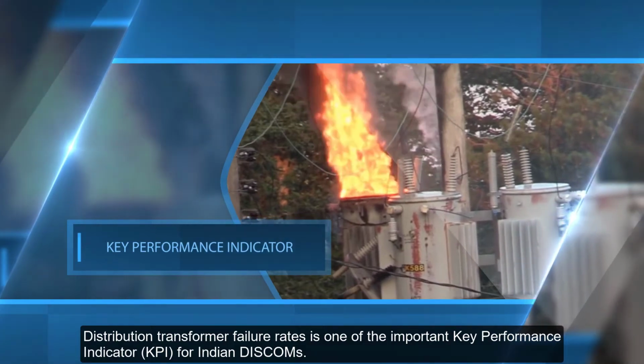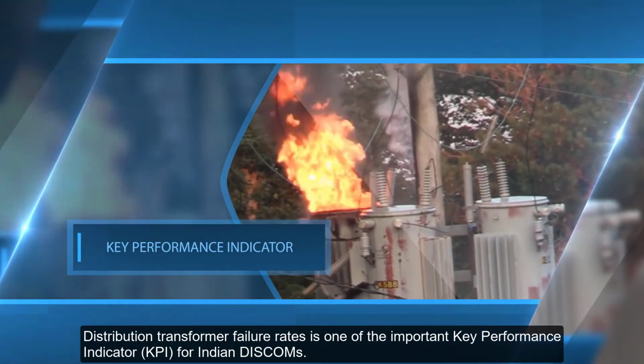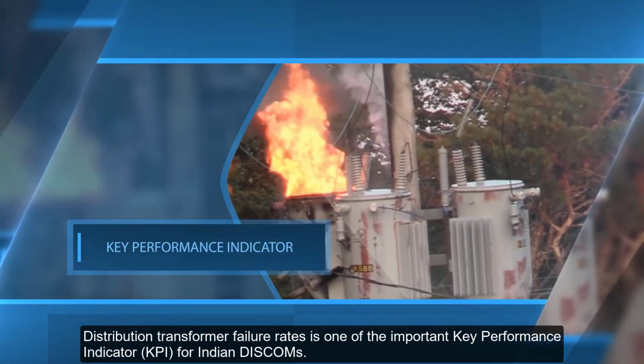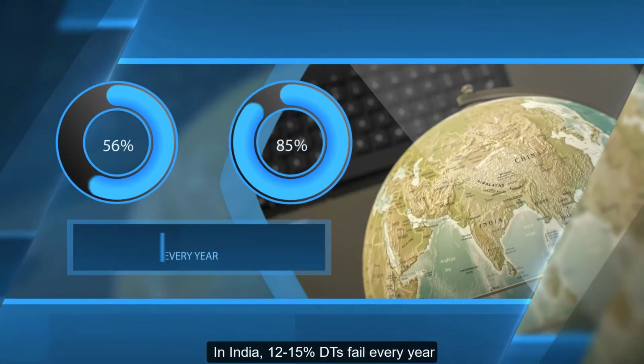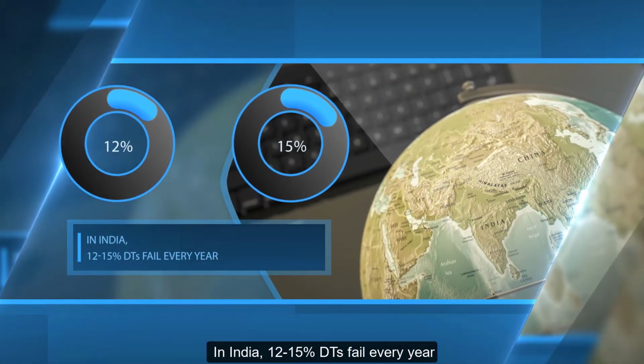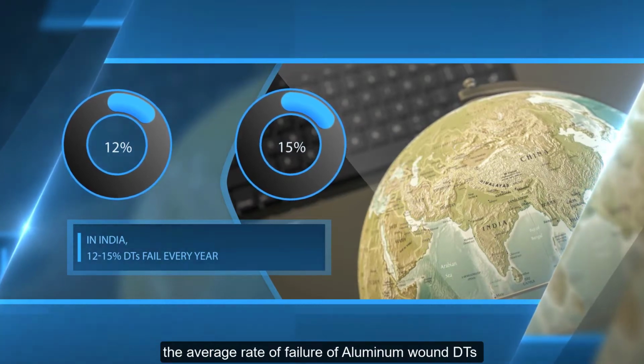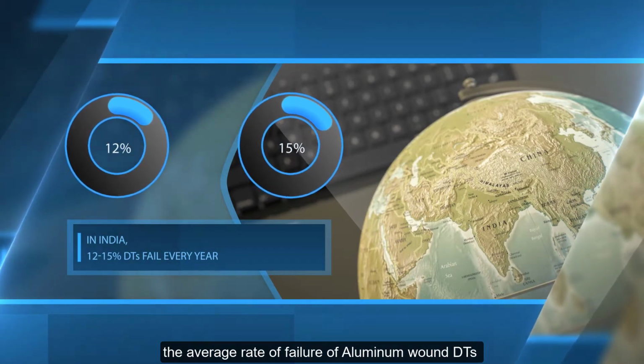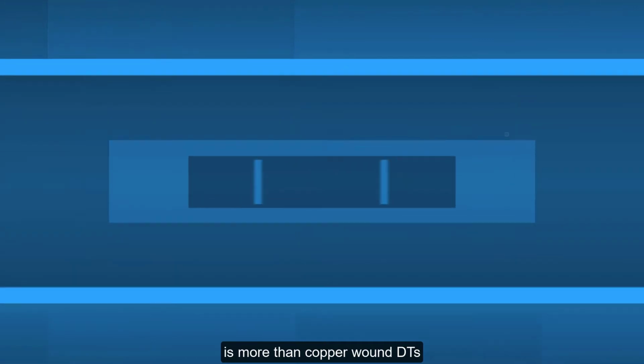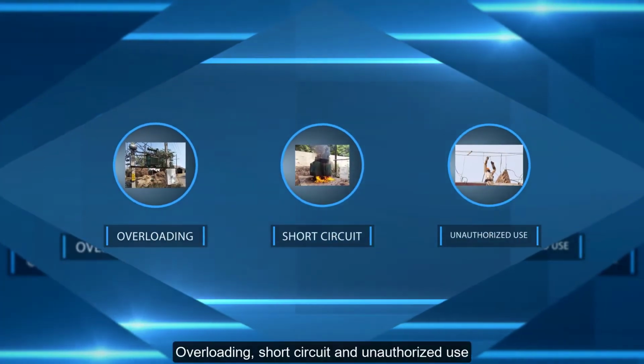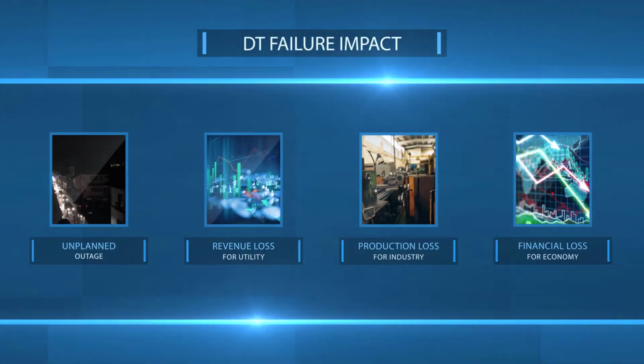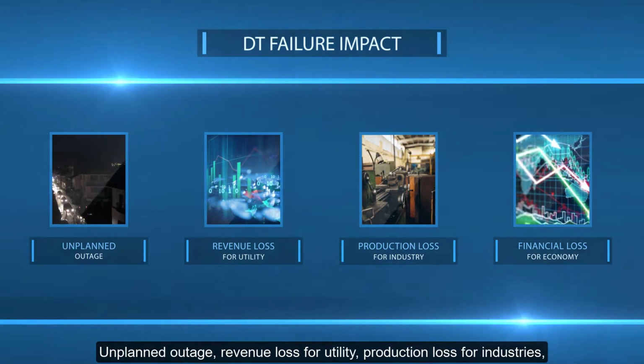Distribution transformer failure rate is one of the important key performance indicators for Indian discoms. 12 to 15% of DTs fail every year, and the average rate of failure of aluminium wound DTs is more than copper wound DTs. The root causes are cited as overloading, short circuit, and unauthorized use. DT failure causes unplanned outage, revenue loss for utility, production loss for industries, and financial loss for the economy.